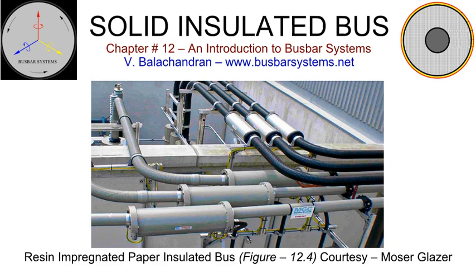The cross-section of the laminate will depend upon the ampacity. The length of the site joint assembly depends upon the voltage. Since the joint is made in the air, adequate creepage distance needs to be provided. The site joint cover should extend beyond the earth ring on the insulated conductor to limit the field strength. The inner surface of the site joint enclosure has a conducting shield which is kept at the same potential as that of the conductor by a spring-loaded conductor. The outer surface of the site joint enclosure has a conducting shield which is connected to the earth. This arrangement ensures that there is no discharge from the live conductor and the enclosure is touch safe.